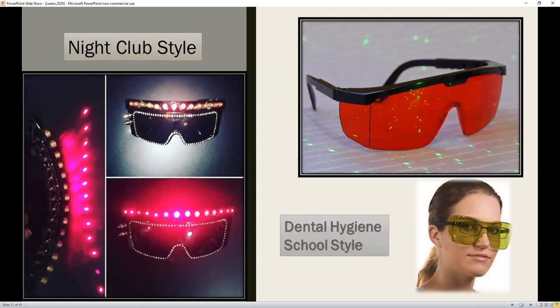So here are some different types of laser glasses. Some of them are supposed to be funny, but the nightclub style is used to protect the DJ or the club workers from the laser light shows, okay? And the one on the right is more of what you'll find in dental offices. They come in different colors from green to red. And the important thing is to make sure that the safety glasses are manufactured for the laser type that you are using.